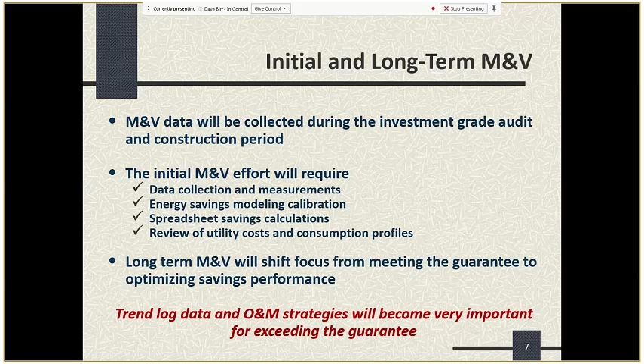There is a shift as you move from the initial stages of M&V, where measurements are taken during the audit phase or during and immediately after construction. In the long term, M&V shifts focus from meeting the guarantee to optimizing savings performance, where the goal is continuous improvement in project performance over time. That's when trend log data from the EMS system and O&M strategies become very important for exceeding the guarantee performance over time.